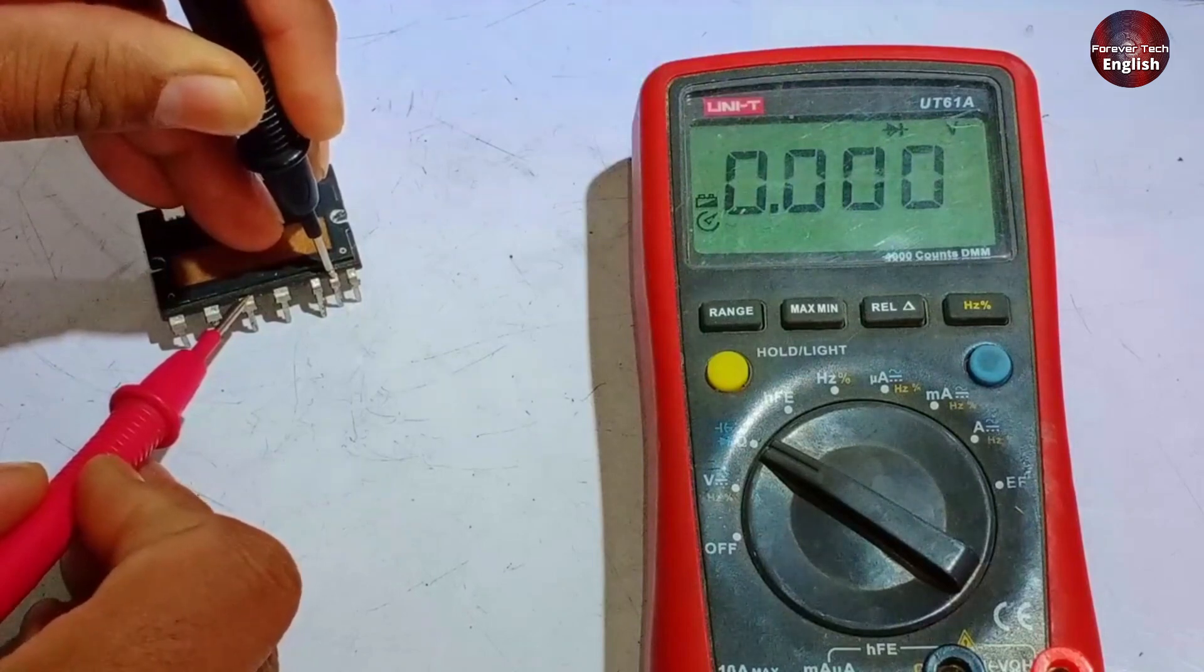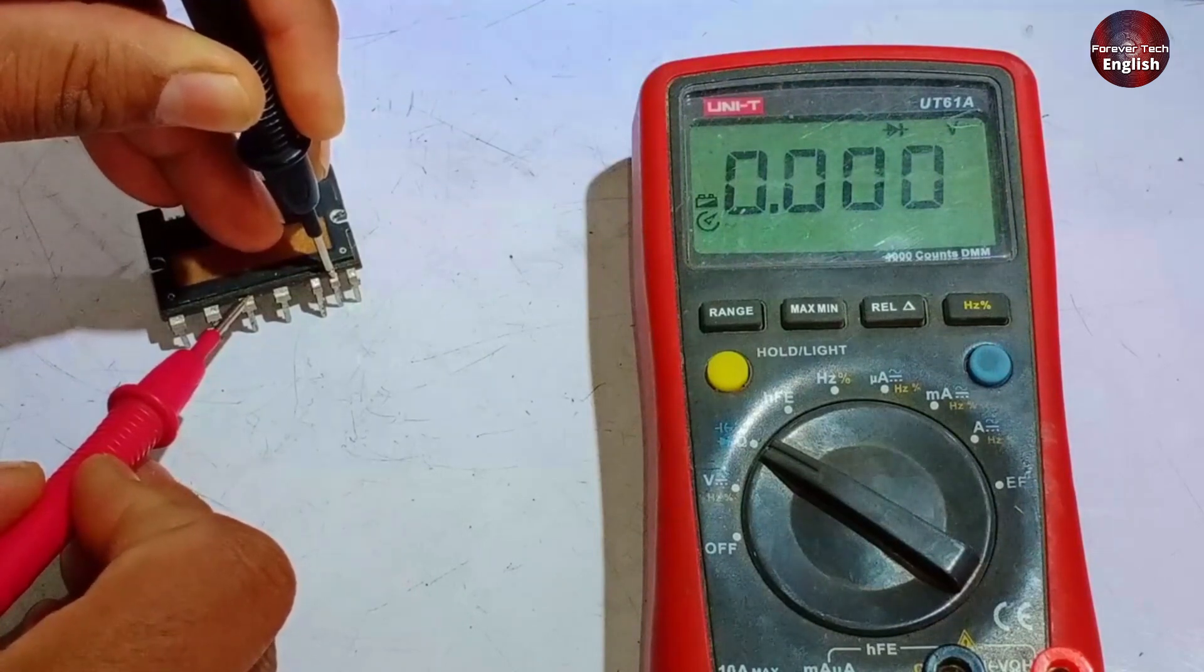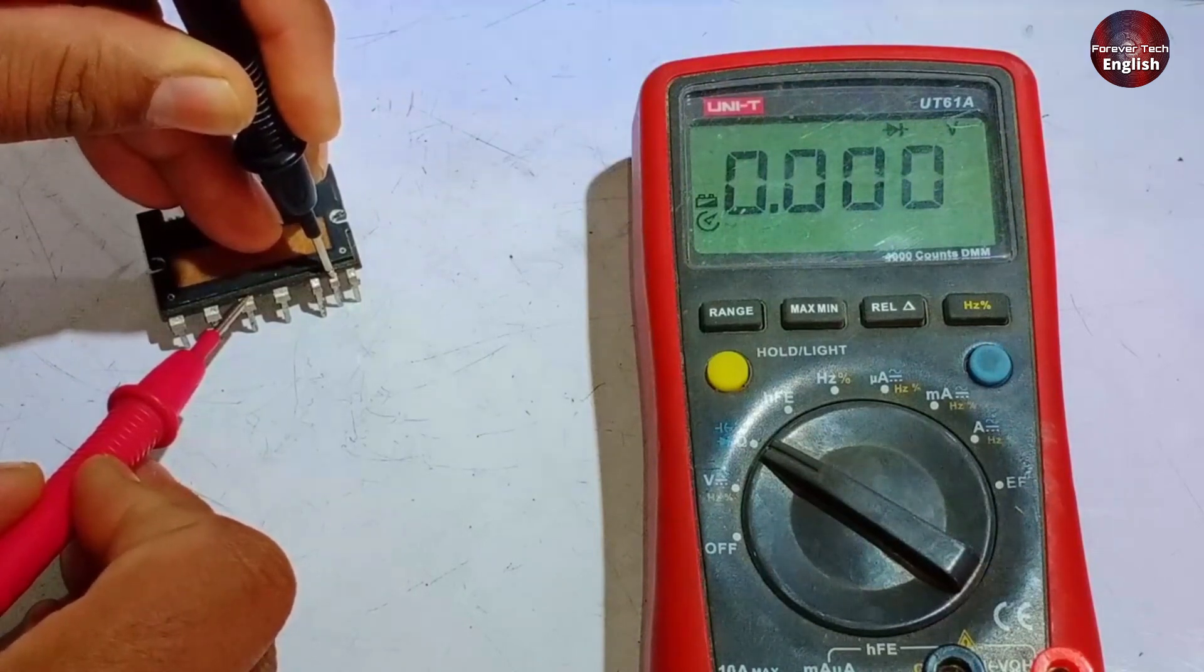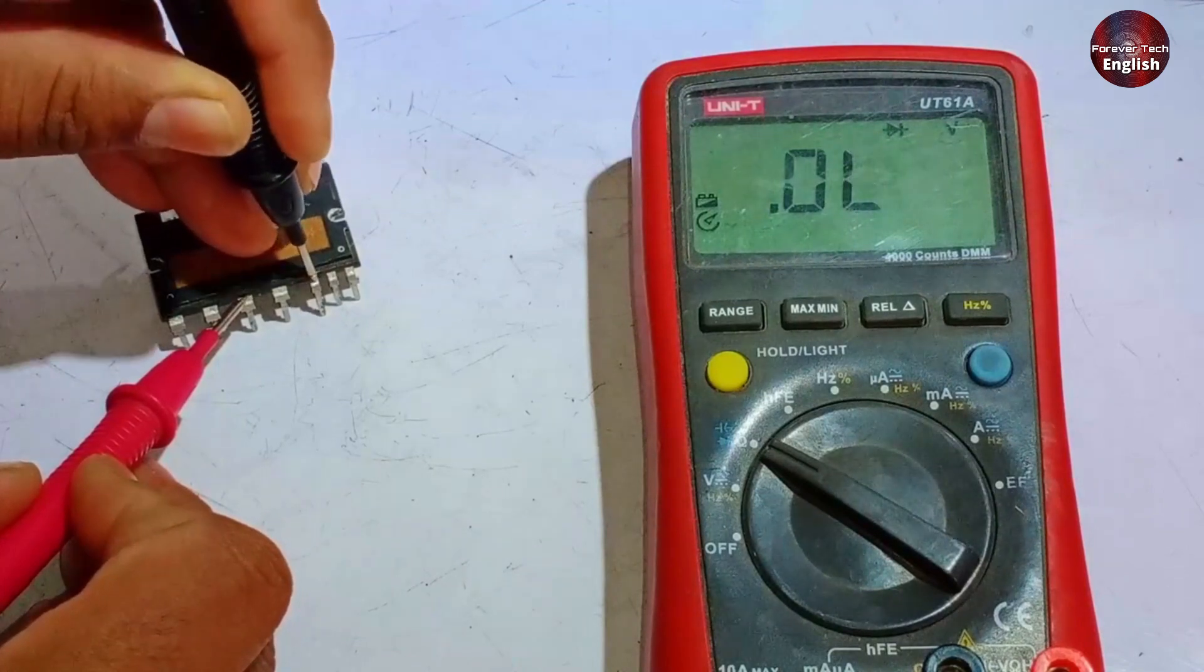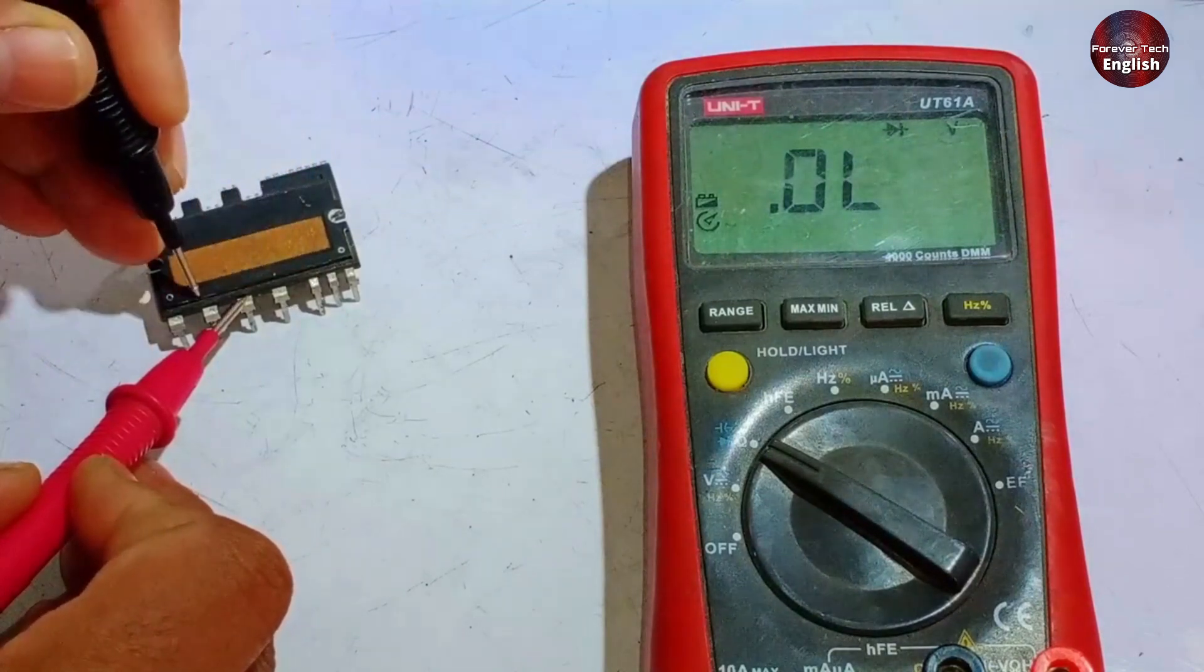However, since the IGBT is shorted, it is showing zero, but if it were in its original working condition, no value would be displayed. Similarly, no value should appear at the next point either.